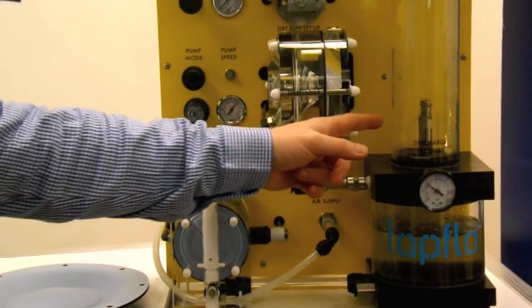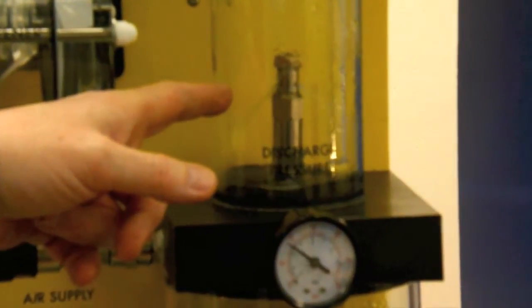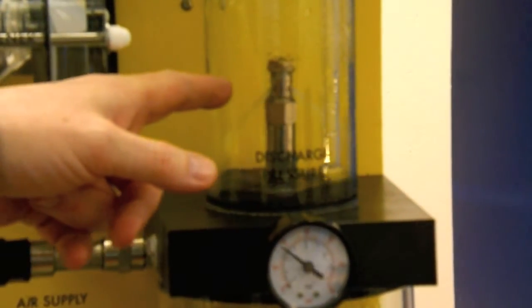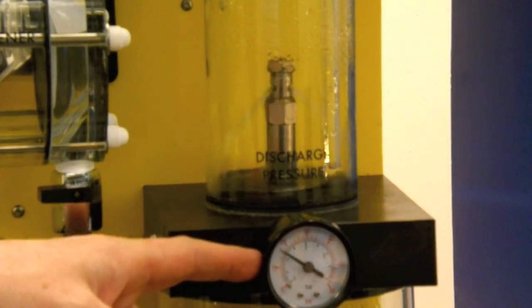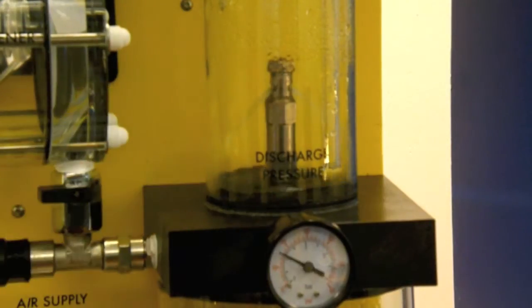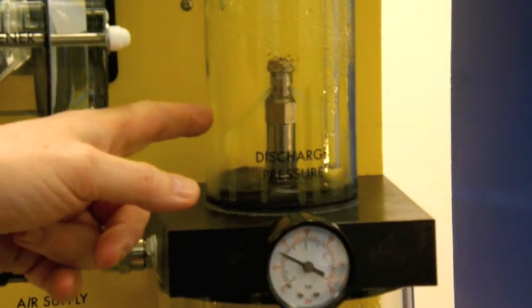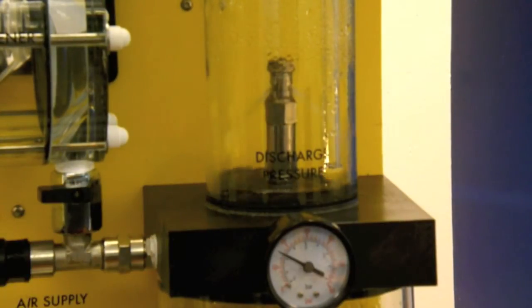As with all diaphragm pumps you'll notice we have a pulse discharge and you can see that here on the discharge nozzle in the top tank and also on the pressure gauge here. This pressure gauge is measuring the discharge pressure coming through this nozzle so you can visually see the pulses and you can also see it registering on the pressure gauge.